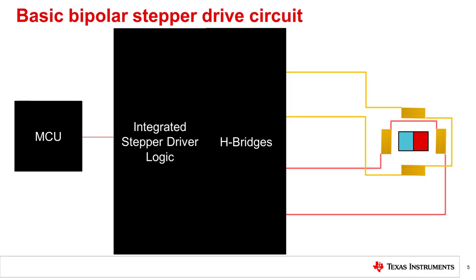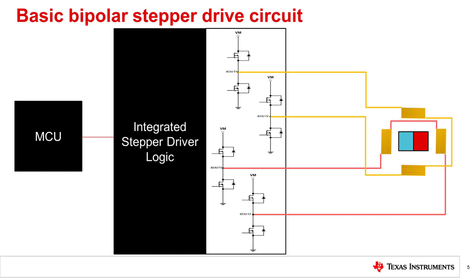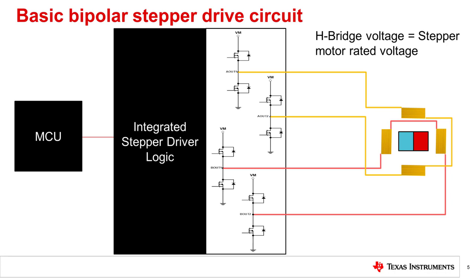The internal H-bridges of the stepper are now visible to clearly show the operation. Stepper motors can be driven using voltage or current. Voltage control is the simplest method to drive a stepper motor. The voltage of the H-bridge is set to the rated stepper motor voltage. The current is limited by the resistance of the motor and does not exceed the rated value. The speed of the stepper motor is limited because the current change is limited.